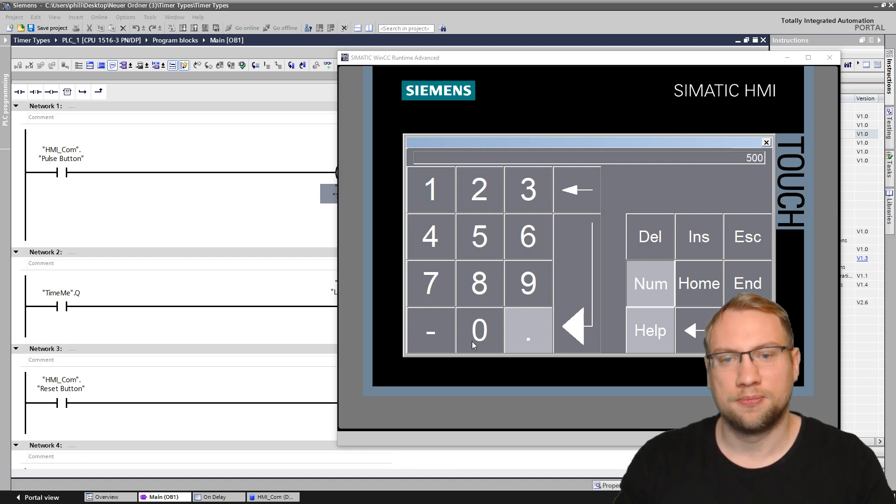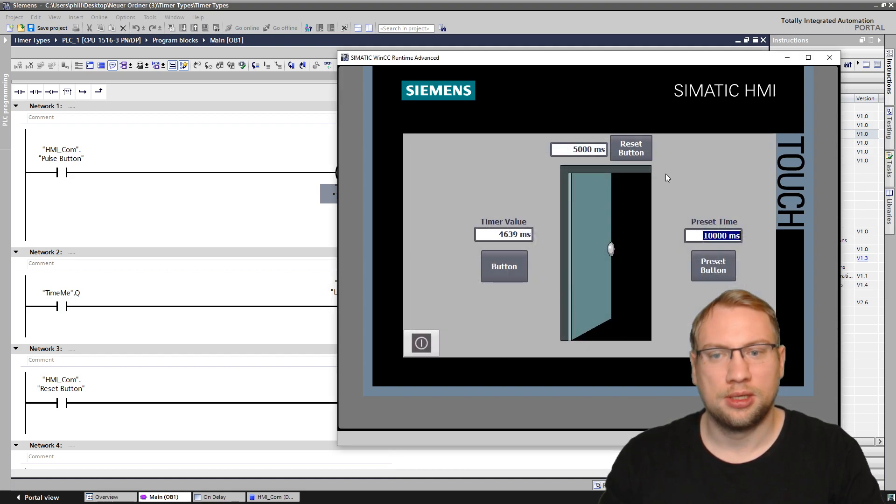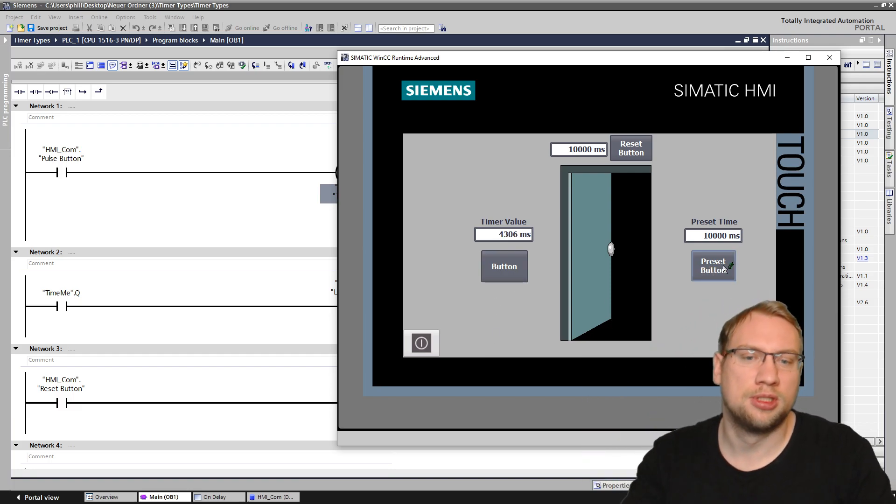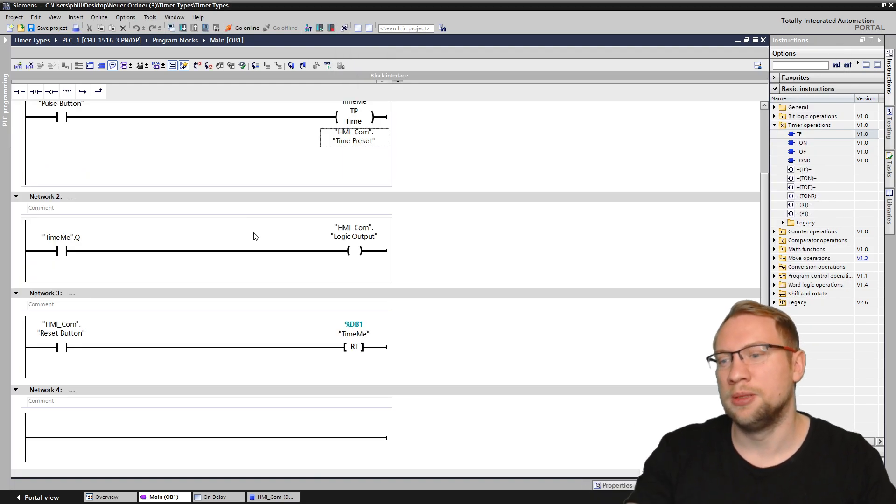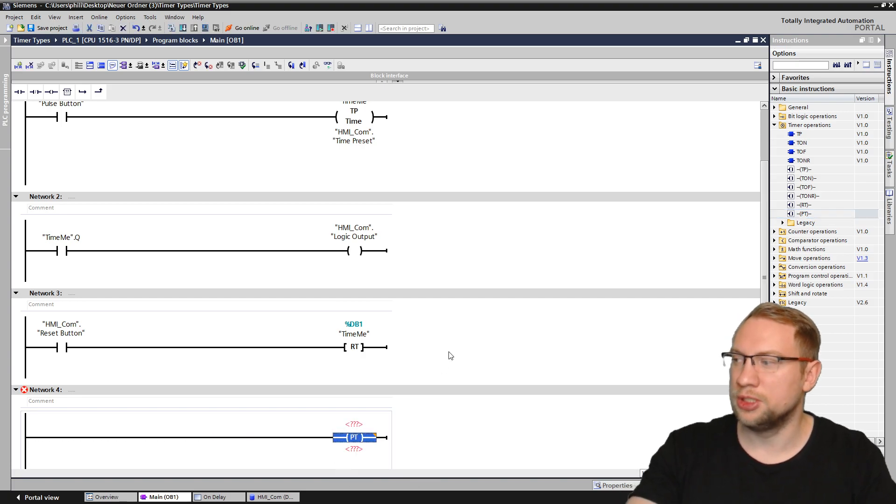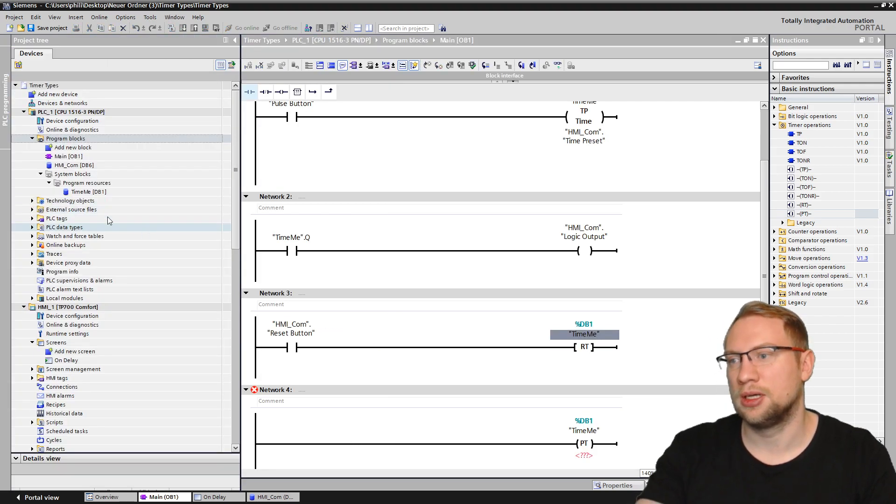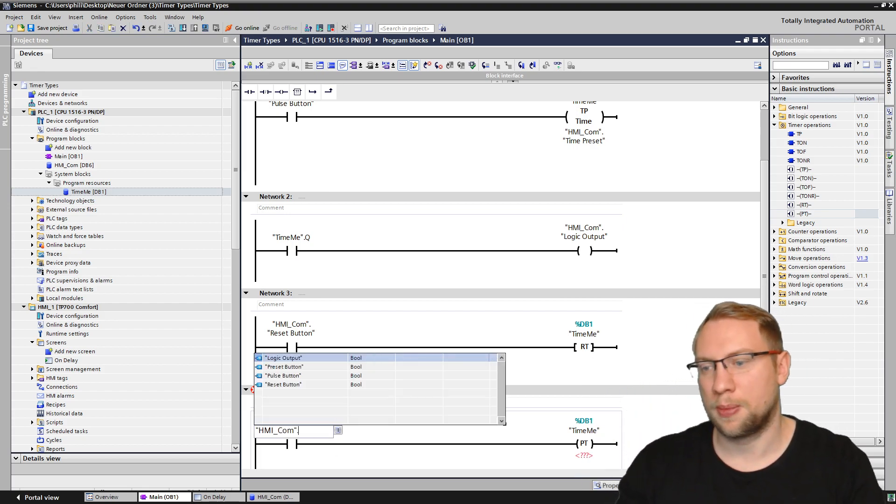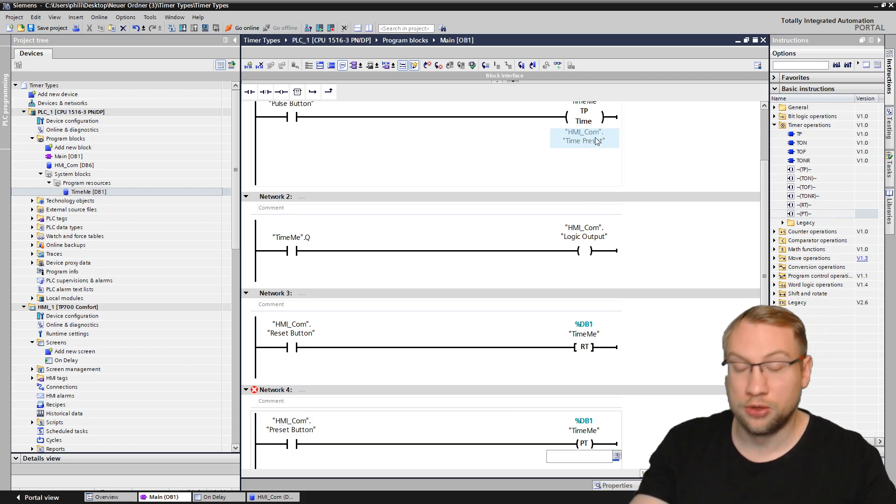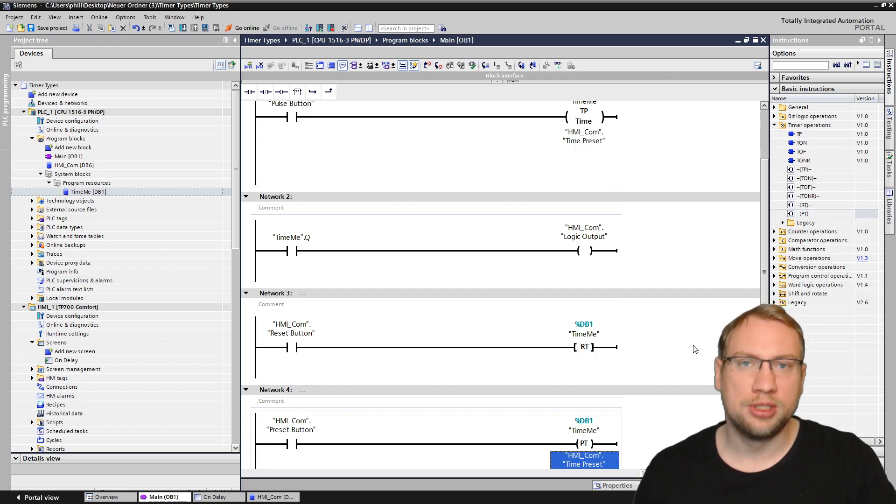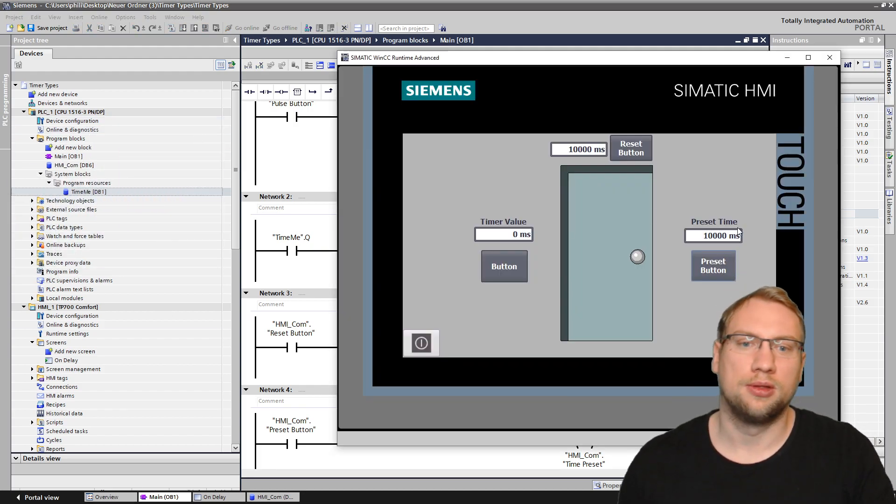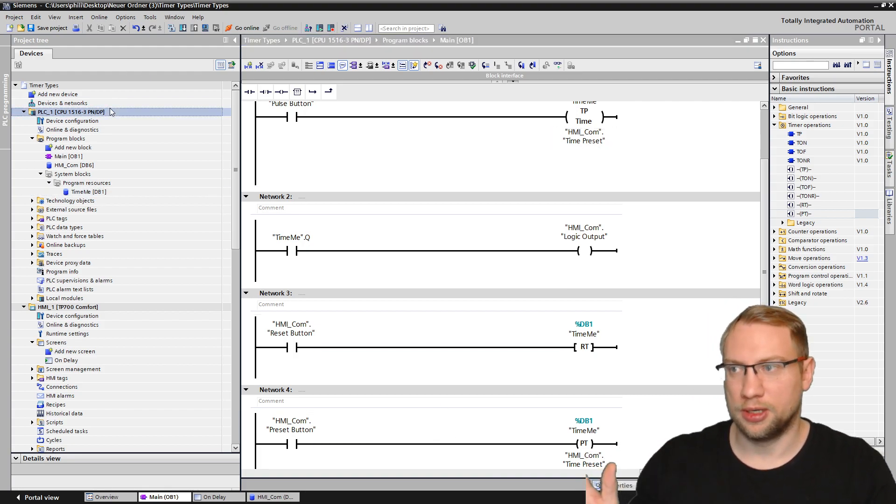Like right now I can say 5,000 and it will be 5 seconds. If I now say 10,000, nothing will change until the next time I press the button or I restart the timer. That's silly. I want to use this preset button to actually go right now and change it even when it's running. Even when it's running, we can manipulate it and this is called a preset. We can take the PT instruction, preset timer. I guess I have to take this one here again. This is my timer database. Then I need the button I have prepared. It's my preset button. Not reset, preset. And I need to preset it to a time. I just want to take the preset time that I'm actually putting in, that I'm putting in on this field here. That's it already. That's it, how we can change the time even when the timer is running.